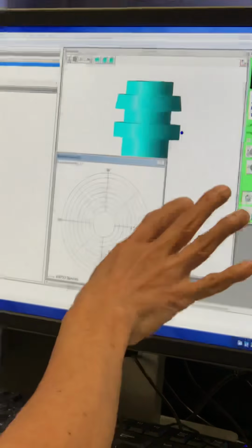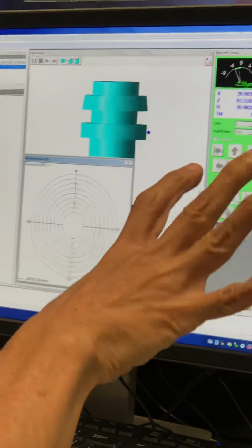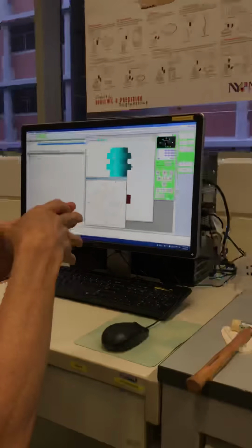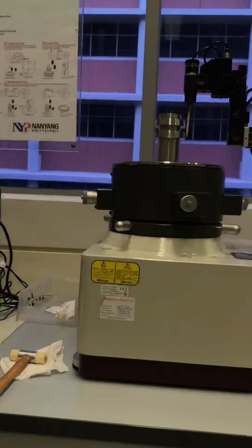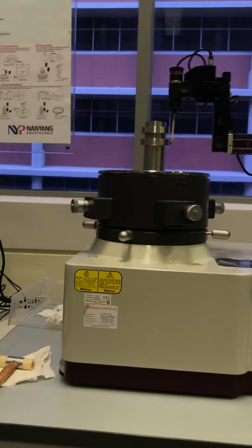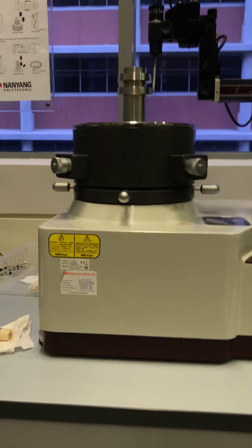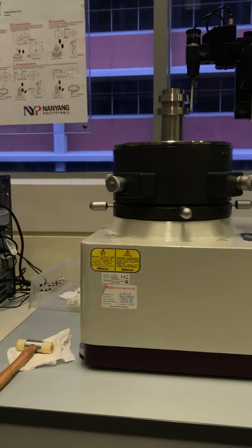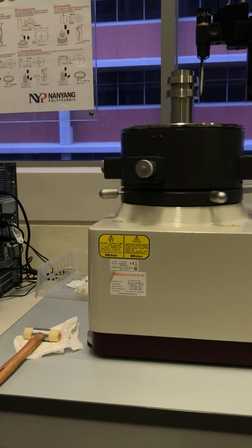So the magnification is very important in roundness. You need to magnify the radius error. After that you need to stop the table. So you can see there's a peak here. Can you see?